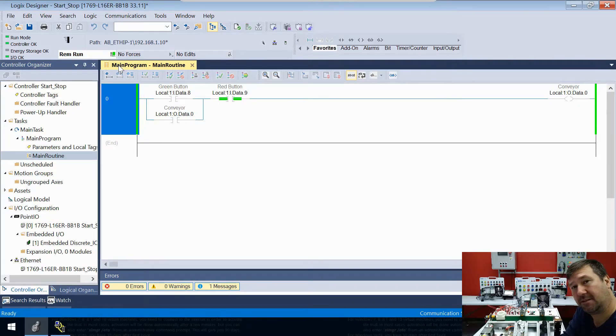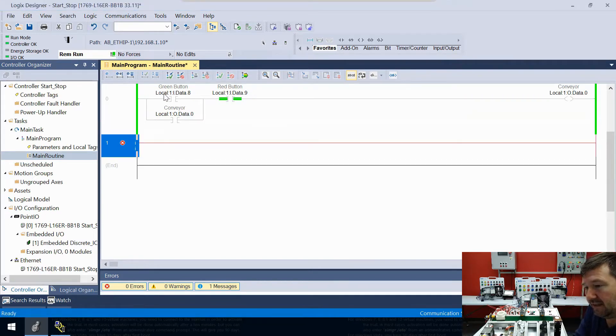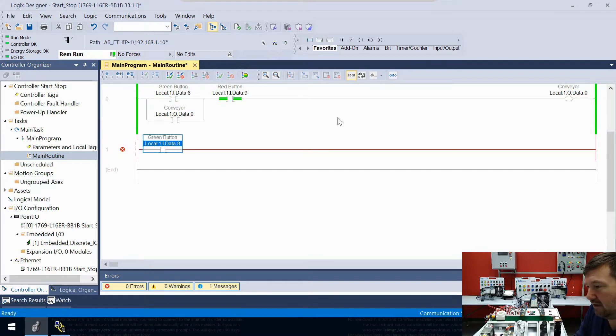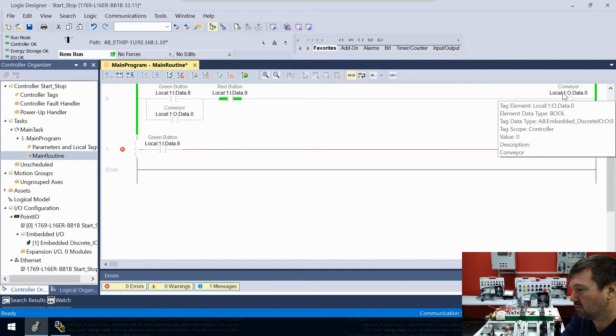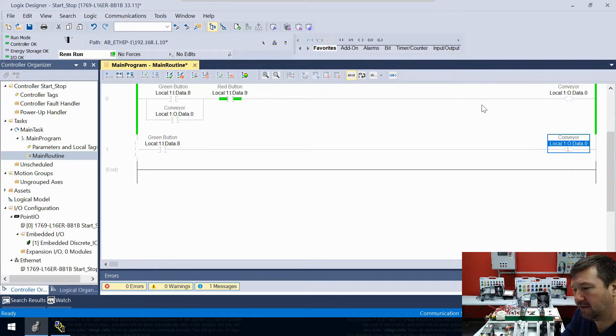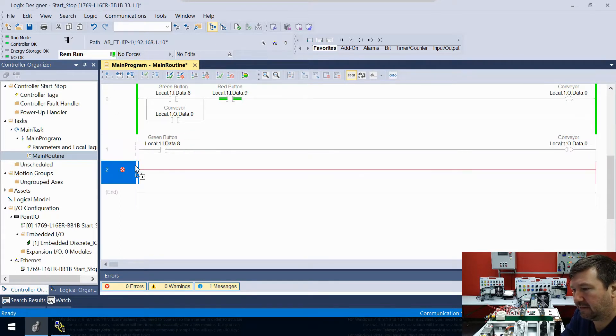Let's go back online. Now we're going to make a latch/unlatch — do this exactly in the order I do, because we're actually going to bring this rung back to show a few other things. First let's create a new rung, then copy our green button and paste it down here, then get a latch instruction, and drag down that address for our conveyor.